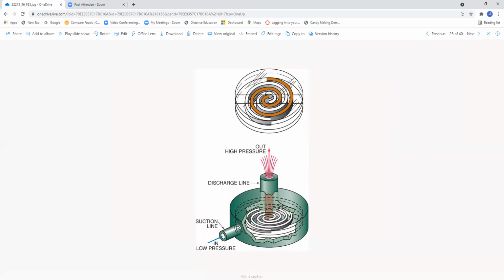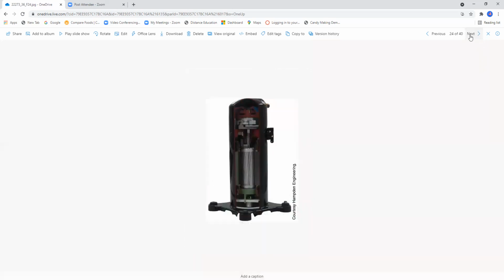This is a very efficient design, very few moving parts. This is proven technology. I've installed lots and lots of these scroll compressors, and I will tell you they work very, very well, and they last a long time. This is a side view of a scroll compressor, and these things, like I said, work extremely well. Your scroll plate, your fixed and orbiting scroll, your motor section, and of course your refrigerant connections, your electrical connections are here.